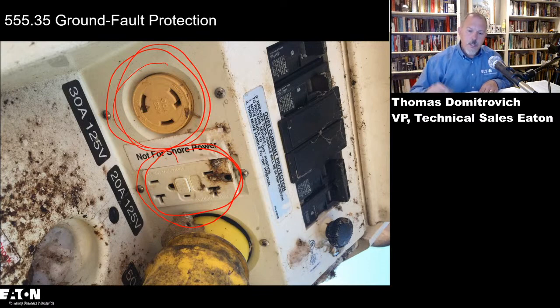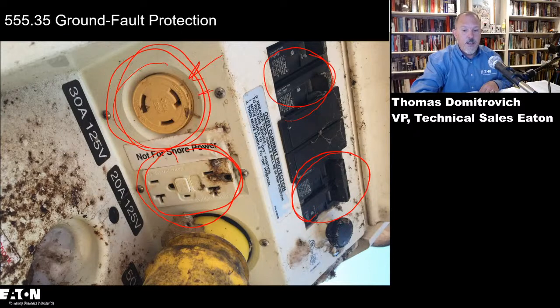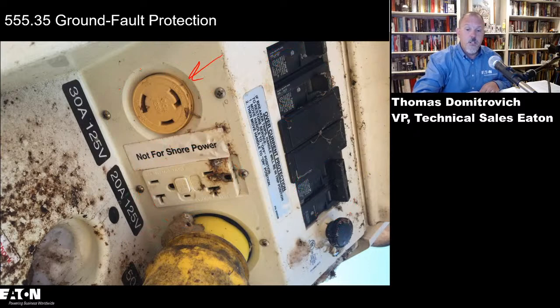So in any case, this shore power now has to have protection where before it did not. You'll notice these are standard thermomagnetic breakers in here, and the only way to protect a 50 amp or a 30 amp receptacle outlet is going to be through a GFCI circuit breaker. And that will be in the pedestal. And this pedestal is required because you need to have a disconnect for that boat. For whatever you're supplying shore power to, there's a requirement in 555 to provide a disconnect, and it has to be within so many inches of that receptacle. And the best way to get that done is through a marina power outlet. And we'll walk through that as we move forward.